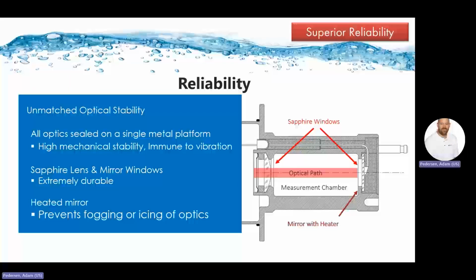All optical components are mounted on a single metal platform, which provides stability of measurements even in high vibration environments. So the dual path length design compensates for temperature, humidity, and particulates in the environment. The heated optics eliminates the adverse effect of moisture in high humidity applications. And the sapphire window is going to be highly scratch resistant. In fact, a diamond is going to be the only stone that's harder than the sapphire. And you can simply clean this unit with a damp cloth or compressed air.